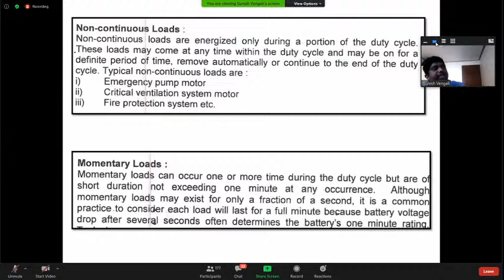So each and everything you need to define your battery cycle clearly. Then you need to size what your loads are impacting, required for your battery, and based on that you need to size your battery using the IEEE standards. After finalizing your battery, you need to fix your battery autonomy. Second, after that, you need to check what is your battery recharging time.